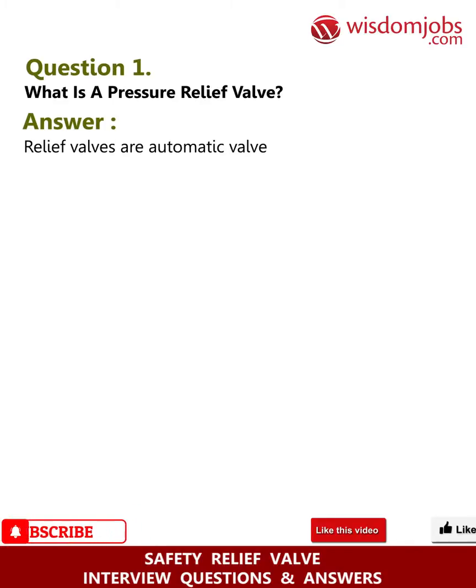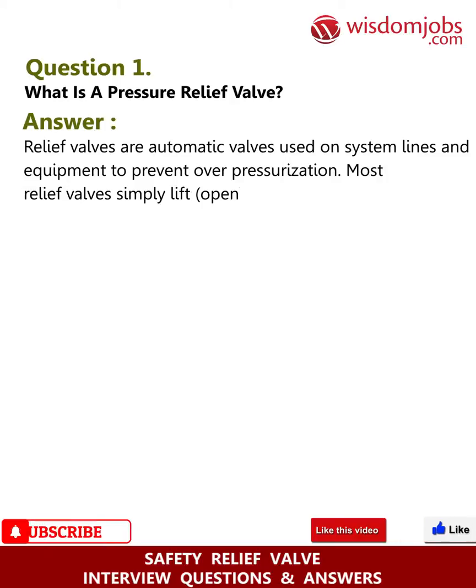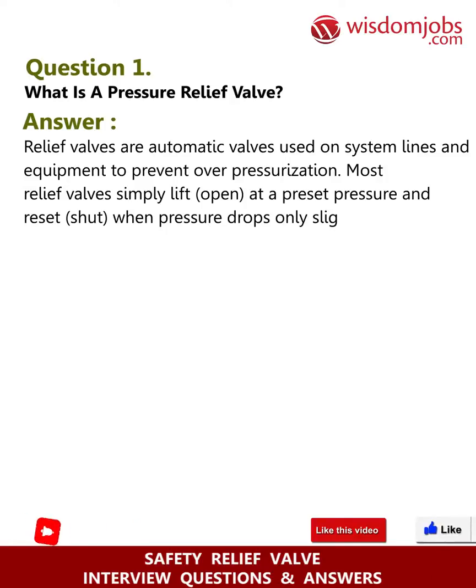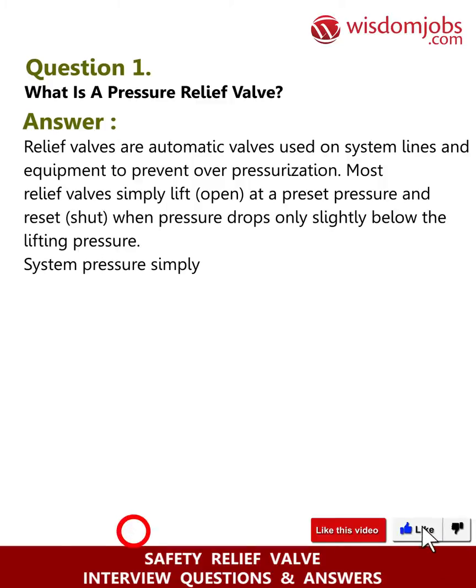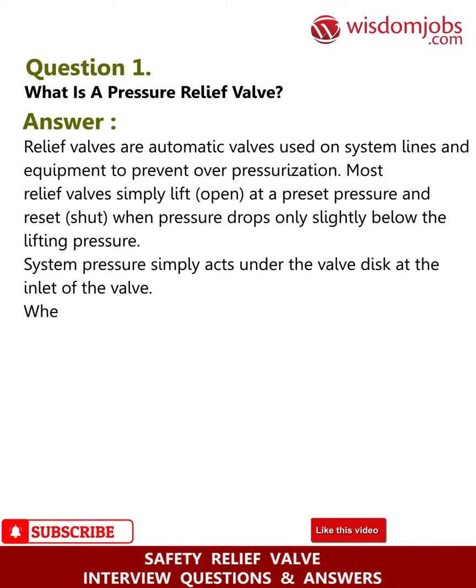Question 1: What is a pressure relief valve? Answer: Relief valves are automatic valves used on system lines and equipment to prevent over-pressurization. Most relief valves simply lift open at a preset pressure and reset shut when pressure drops only slightly below the lifting pressure. System pressure simply acts under the valve disc at the inlet of the valve.